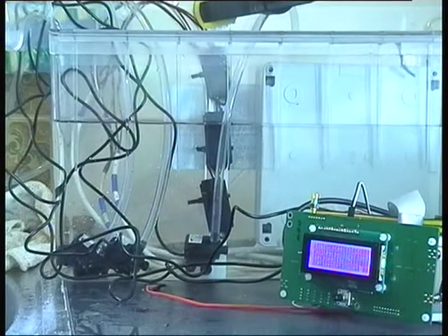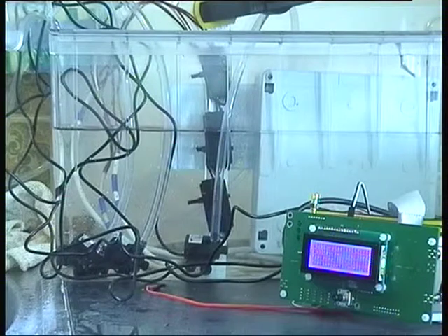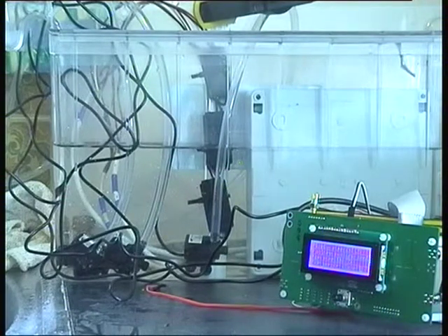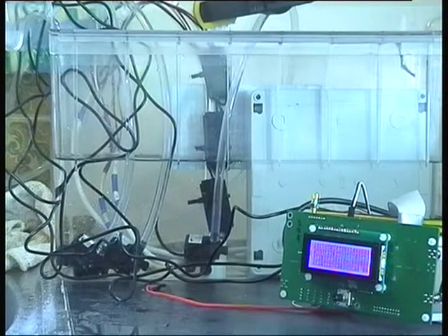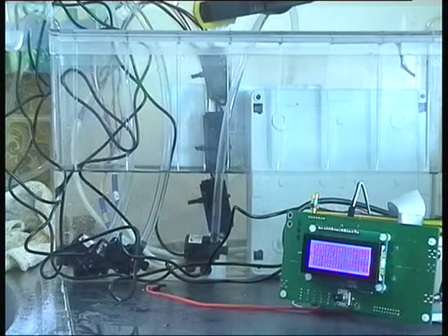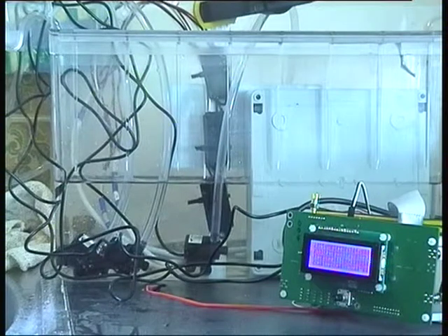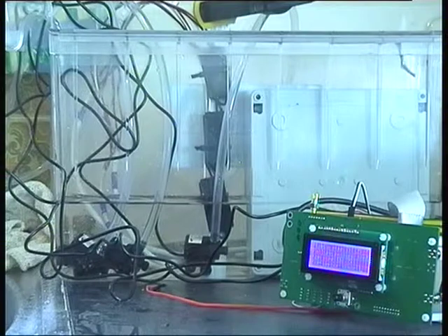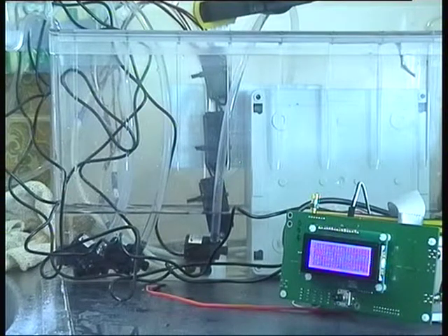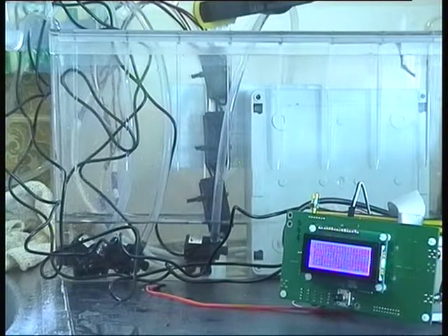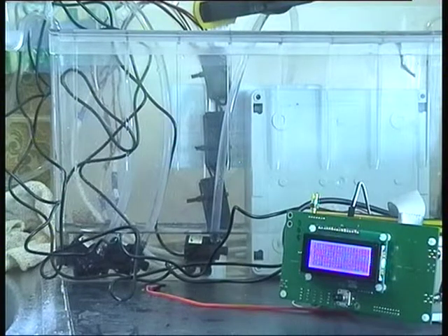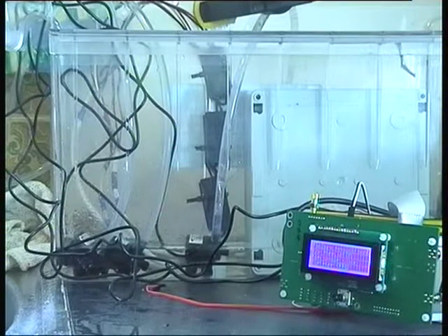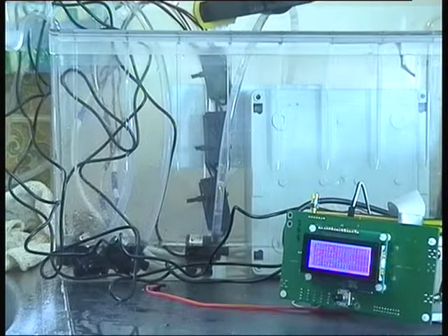The top sensor is now clear, but again there will now be a time delay before the associated pump is switched off. Again, this is programmable. It will be a function of the size of the tank and the capacity of the pumps. In this case, the time delay was 45 seconds, which is approximately correct.